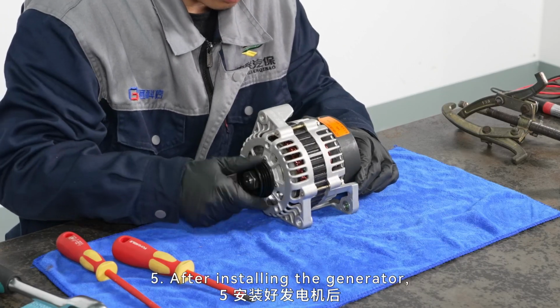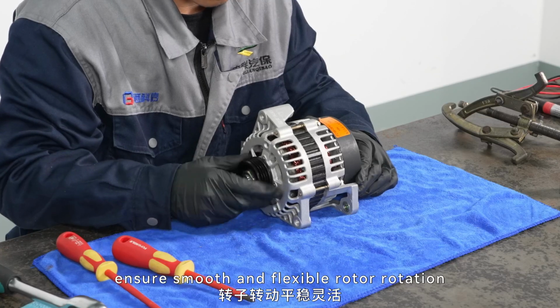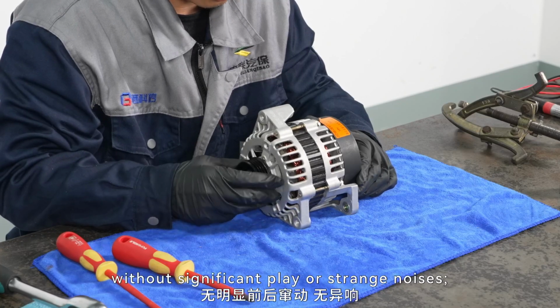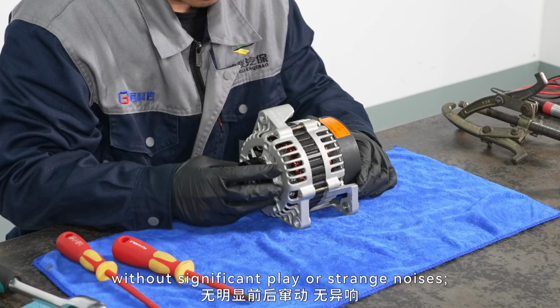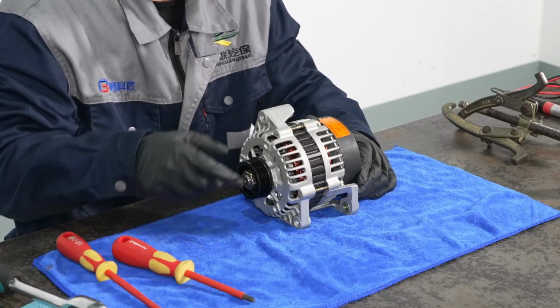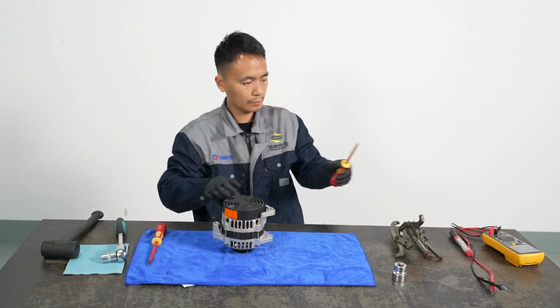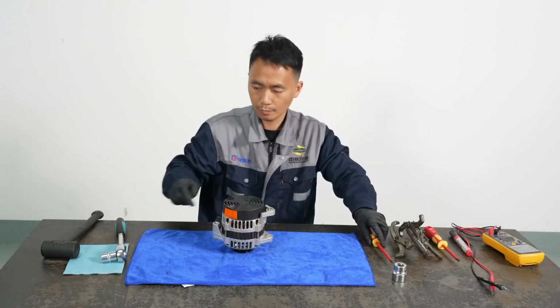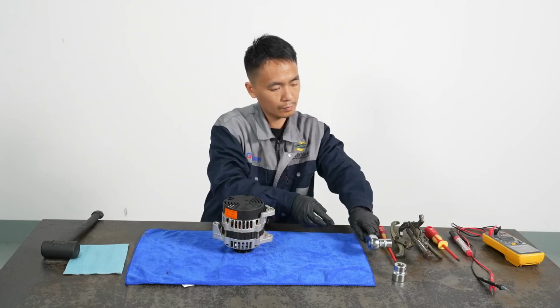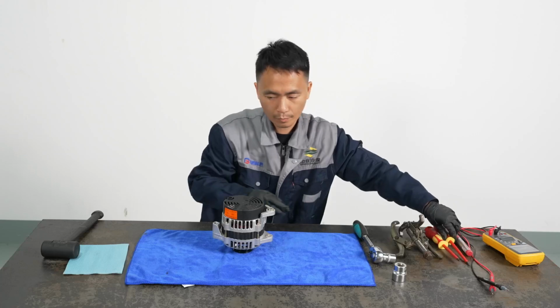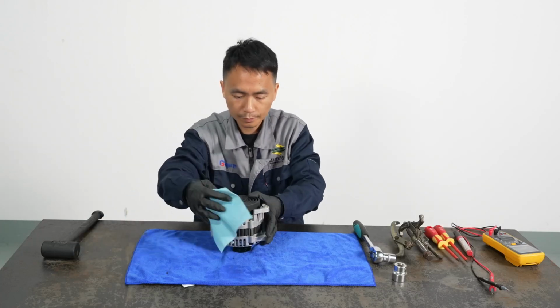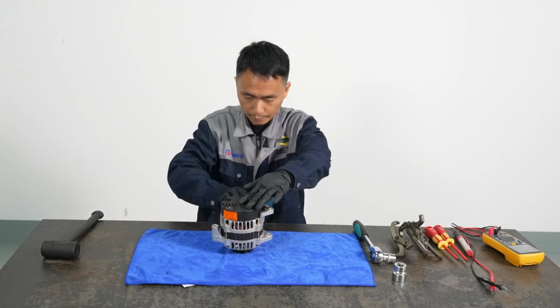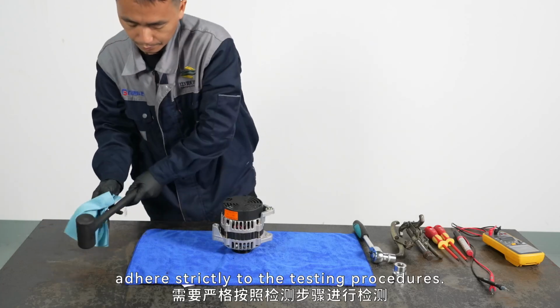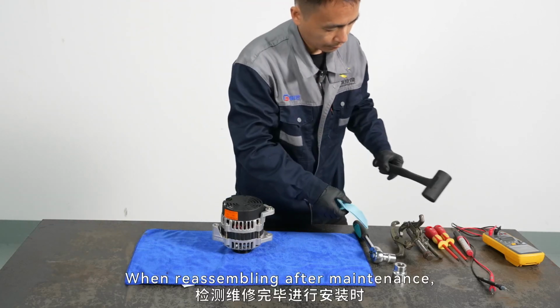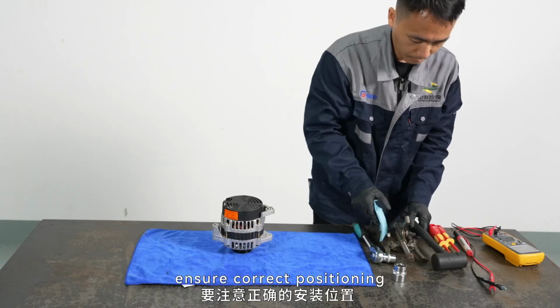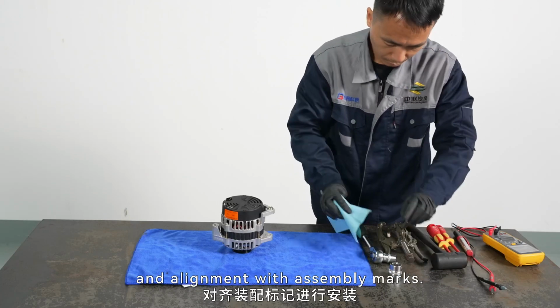5. After installing the generator, ensure smooth and flexible rotor rotation without significant play or strange noises. 6. Clean up. During generator maintenance, adhere strictly to the testing procedures. When reassembling after maintenance, ensure correct positioning and alignment with assembly marks.